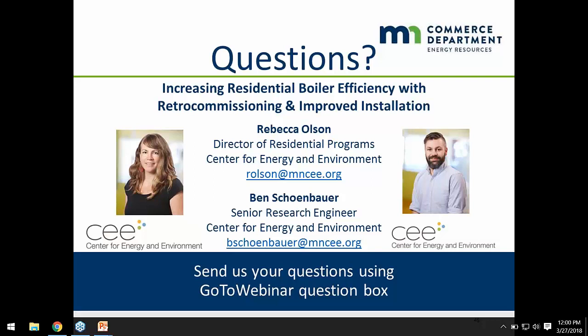And so that was good to ensure that it wasn't always oversized or always operating at much higher capacities than is needed. In general, we didn't see cycles that were so short that it was really having a huge impact on efficiency, but there are definitely some impacts of that oversizing. It would obviously be better to have a boiler that had a maximum capacity of something like 50,000 BTU and modulated down to 5 or something. But we didn't see a huge impact from that due to the modulation that was present in the boilers.